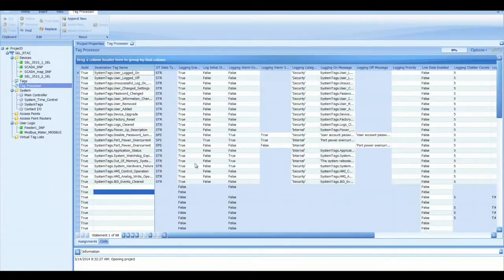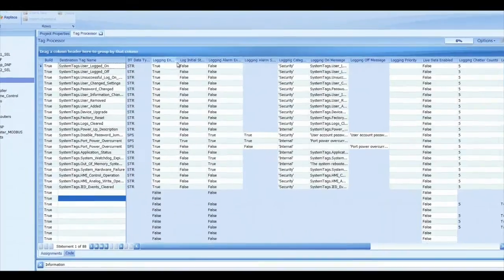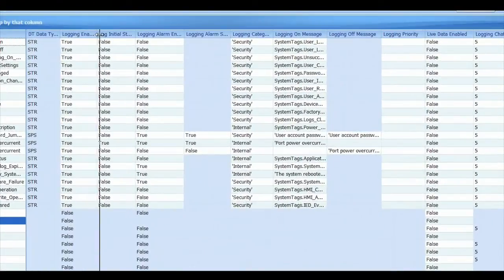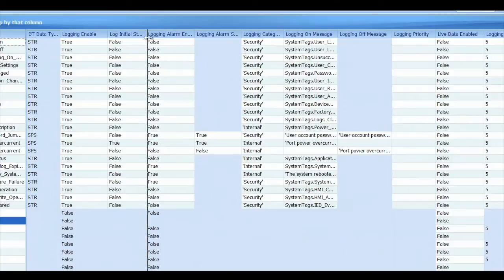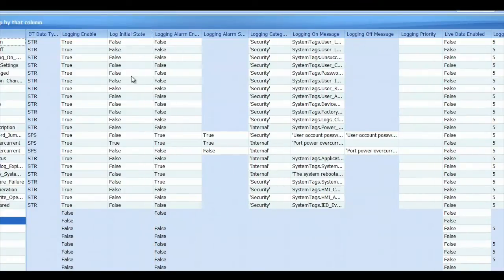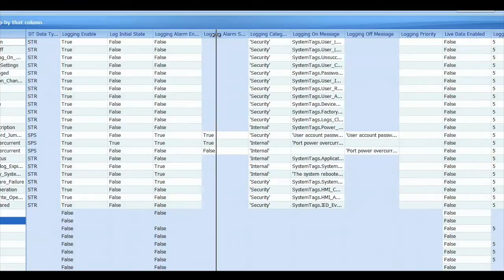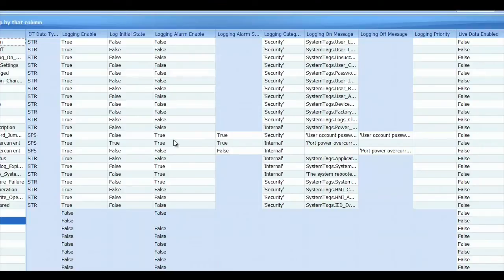So all of these tags that have logging enable set to true will log whenever certain events occur. Let's walk through some of these columns here. There's log initial state, that's basically logging when you first start up. Logging alarm enabled, if you set that to true, then this point whenever it logs it will also go into the alarm log and you can see it will be red or some color that you can configure.